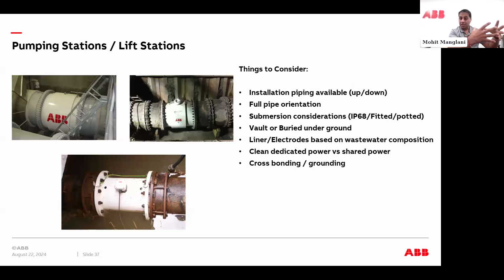That coil housing I was showing you in the beginning, that's not rated for burial. You have to go with the bean can design. You have to make sure the liner and electrodes are based on the wastewater composition that you have. You want to make sure you have clean, dedicated power. Obviously, if you're out in the field and there's not clean power available, that might be a challenge for your installation. And obviously, cross bonding and grounding. You want to make sure that those practices are applied to get the most accurate meter you can get.